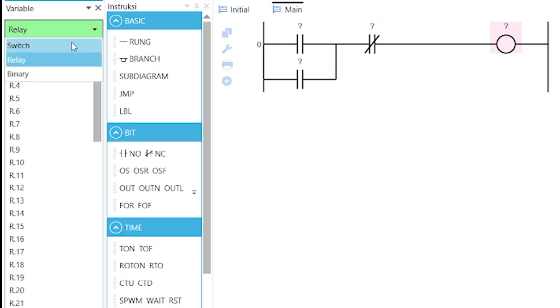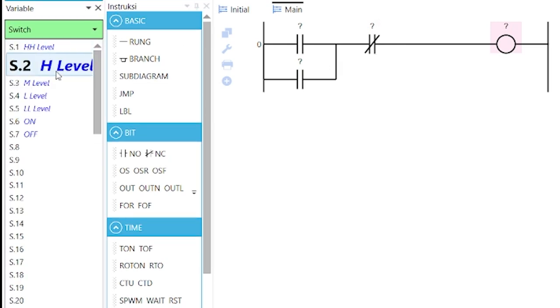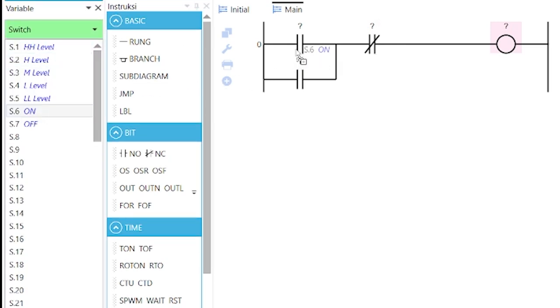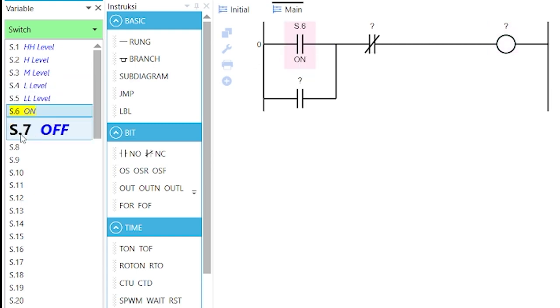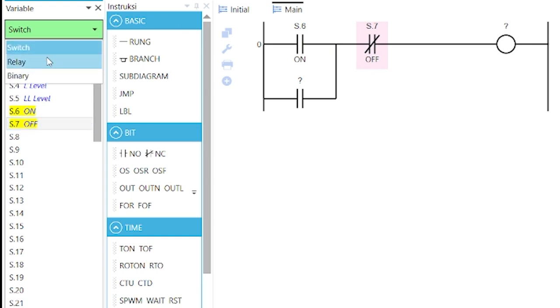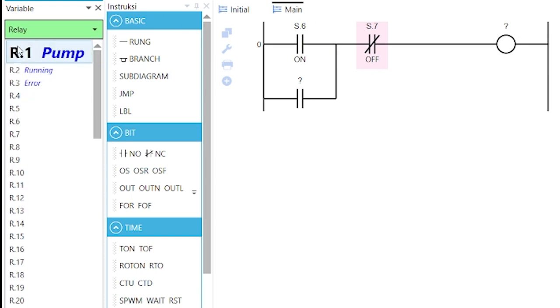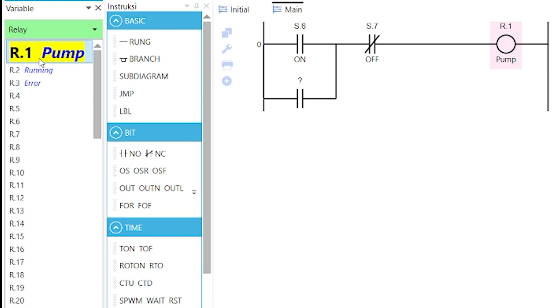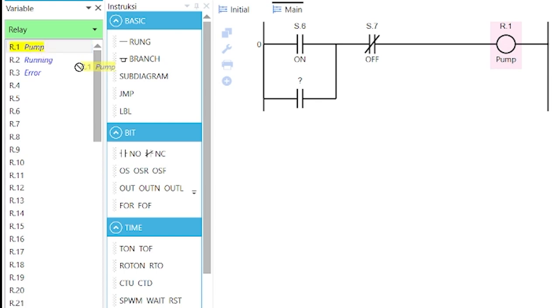Select the ON variable S.6 for the normally open contact, and the OFF variable S.7 for the normally closed contact. Select R.1 for the coil. R.1 should also be the variable for this other contact as a retaining contact.